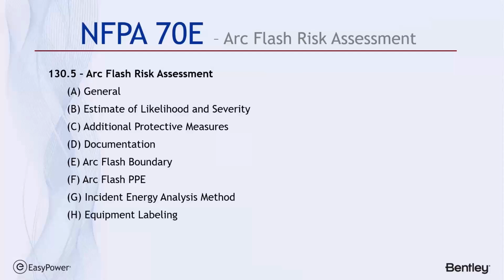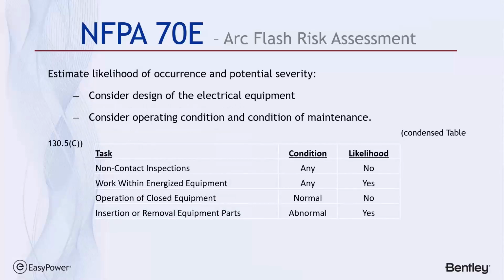So Article 130.5 is the detailed description of an arc flash risk assessment. And it covers everything up to and including equipment labeling. So the purpose of an arc flash risk assessment is to estimate the likely occurrence and potential severity by considering the design of the electrical equipment and the operating conditions and the condition of maintenance. And so there's this table, 130.5C, that gives us some indication of the likelihood of a worst case event. Don't misread it to be a suggestion that you should wear or should not wear arc flash PPE. This actually goes more to the maintenance, considering what maintenance is and condition of the equipment is. And that's an area where things are evolving even as we speak.